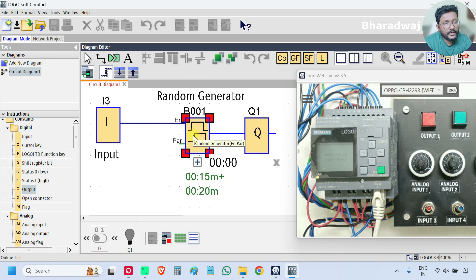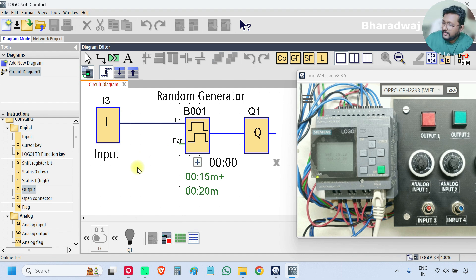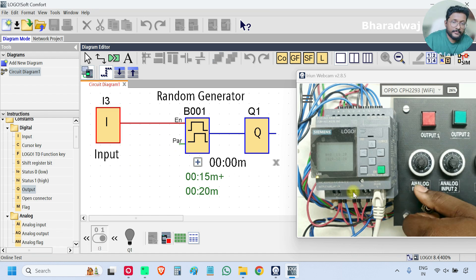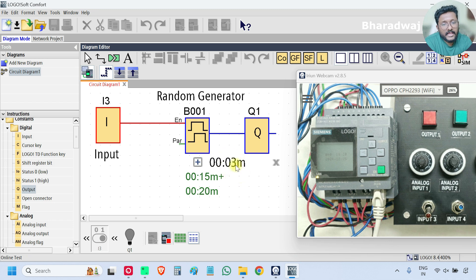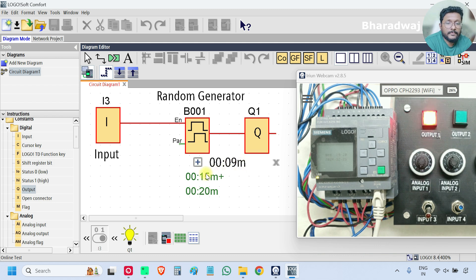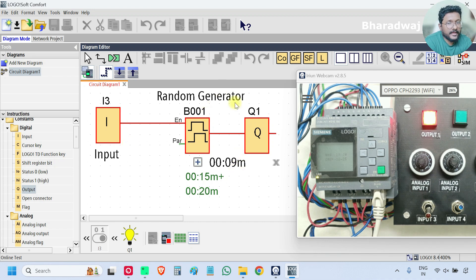I will turn on input I3. The input is on and the timer has started — it will now pick a random value. The maximum it can go to is 15 minutes for on-delay as per our settings. It picked 9 minutes for on-delay; after 9 minutes the output is on — the on-delay is working.